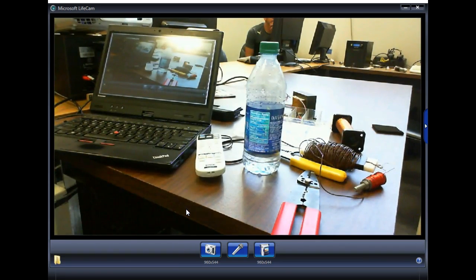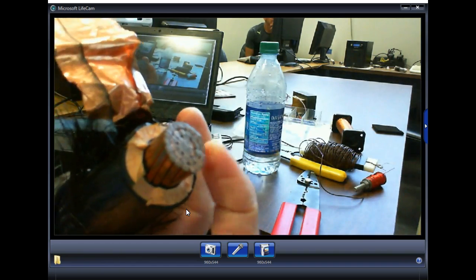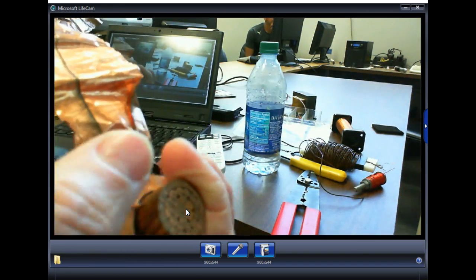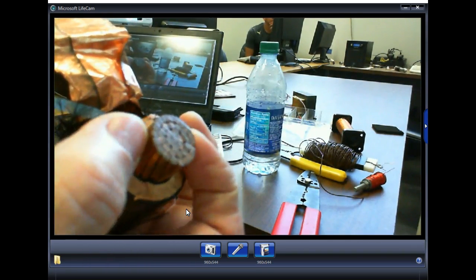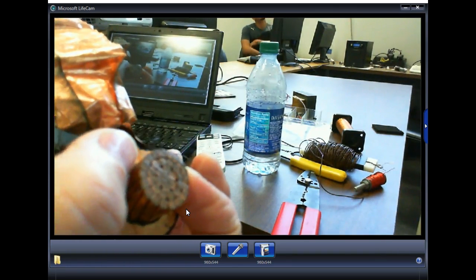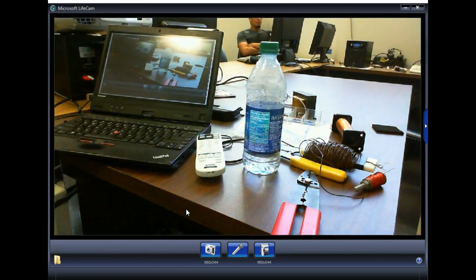This is actually a stranded cable, but you won't be able to bend it much. But we could still roll this up on a spool, right? You understand? So the bigger the cables, but if this was solid, they couldn't even roll that up on a spool, right? So this is a medium voltage cable. I can't remember exactly what it's rated at. We don't have any markings on the cable, but you can literally see these different layers.